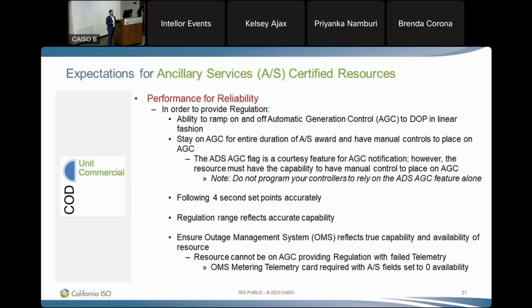So regulation range also needs to reflect the accurate capacity of the unit. We get telemetered in our AGC system the range in which the site can basically provide. It may be from 100 to say 0. That may be the range. They need to be able to regulate within that range.